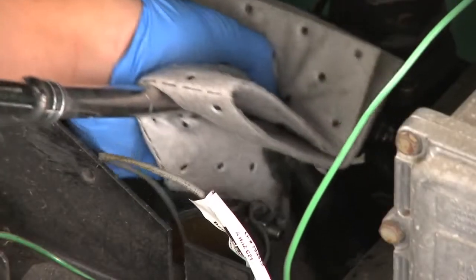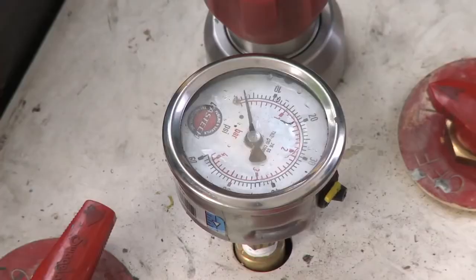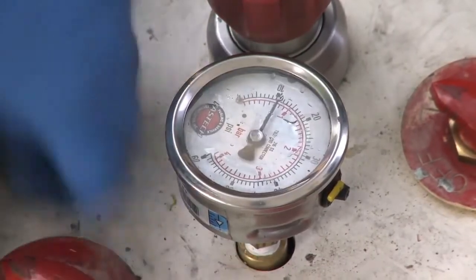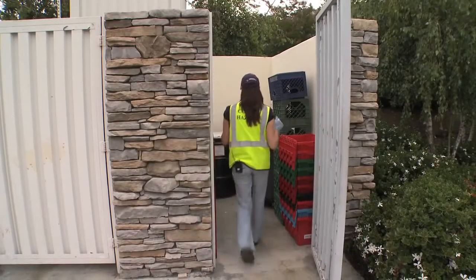On this day at this gas station, not everything passed inspection. One liquid sensor failed. They have 30 days to show me compliance, and we tell them you have to fix it right away or immediately — that way we are not allowing them to be out of compliance for 30 days.